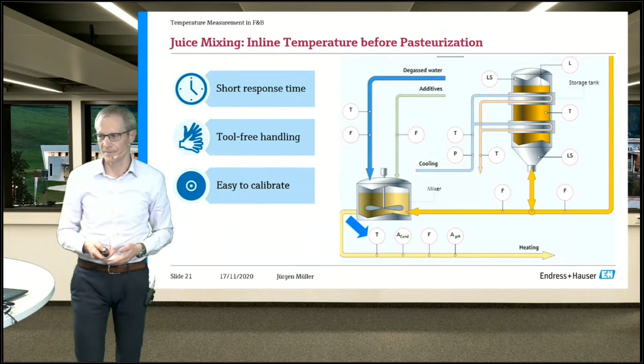It's interesting to have a sensor which you can handle without needing any special tools. What I mean by handling is that from time to time, whenever you use a thermometer, you need to do a calibration. So you need to remove the sensor from the pipeline or tank, do the calibration, and then put it back. If you can do this without tools, it's more convenient, and the calibration itself should be as easy as possible.